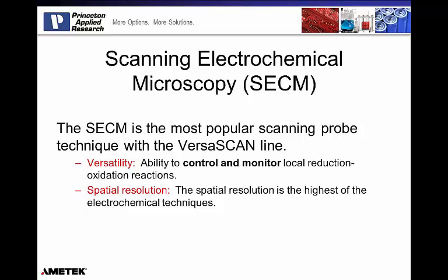I'm going to typically use two potentiostats in an SECM experiment. One potentiostat is going to be used to control the sample, and one's going to be used to control the probe. And so what this means is that since I'm polarizing the sample and I'm polarizing the probe, I can use these potentiostats and I can use electrochemistry and thermodynamics to dictate the reactions that are happening at the probe and at the sample. So it's an incredibly versatile technique, and when we walk through a couple of different types of applications, we can use this to study really any application of electrochemistry, from fundamentals to energy storage devices to corrosion to coatings to biological applications.